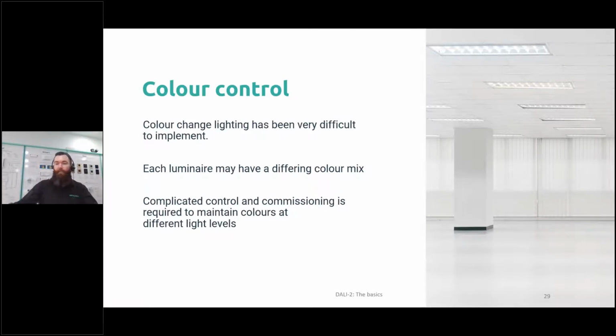Traditionally, when you wanted to do this, you would have a warm white device and a cool white device. They would both have separate addresses, two addresses on each device, and your control system would have to calculate the levels of each one to get your desired lighting. That meant the control was complicated and the commissioning was quite complicated too, because a lot of the time you'd actually have to go to site and measure the color temperature with a color temperature sensing measurement, not a standard lux sensor, and calibrate these devices and their movements over the day.